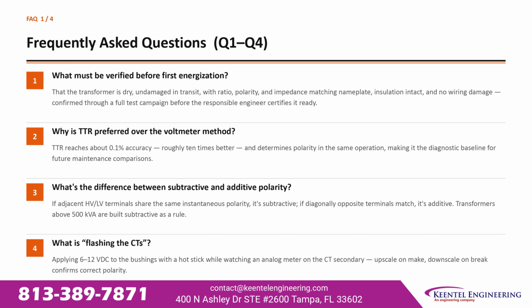What is flashing the CTs? Applying 6 to 12 volts DC to the bushings with a hot stick while watching an analog meter on the CT secondary. An upscale reading on make and downscale on break confirms correct polarity.